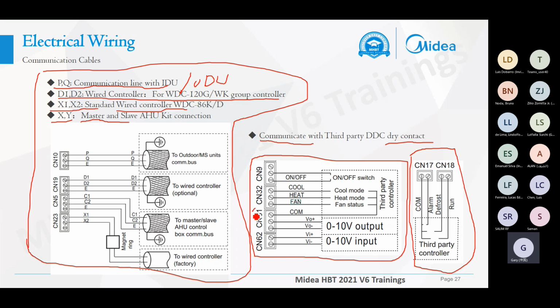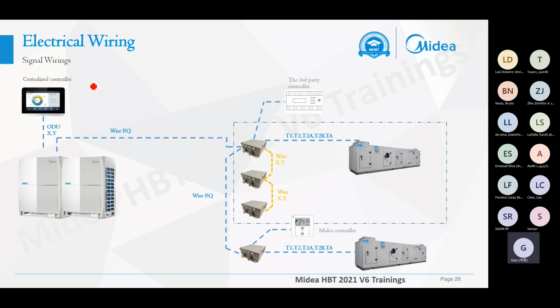Just as in the method before, the CN61 is for the fan controls. And this one you can use to select the temperature control or the capacity control via the 0 to 10 volt inputs. Later we will have the details for this part. Okay, this is the simple schedule for the signal wiring.